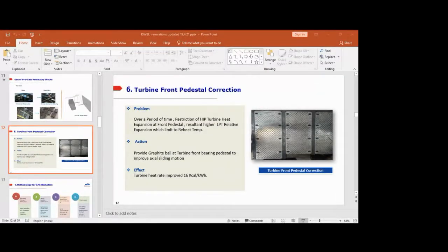Turbine front pedestal correction. Over a period of time, we were facing a restriction of HIP turbine heat expansion at the front pedestal. So it was resulting in higher LP turbine relative expansion, which is limiting the reheat temperature. Whatever restriction we were getting here was shifted to the LP turbine side, so we had to reduce the reheat temperature. Due to this problem, we were not getting our efficiency, and the heat rate was increasing.